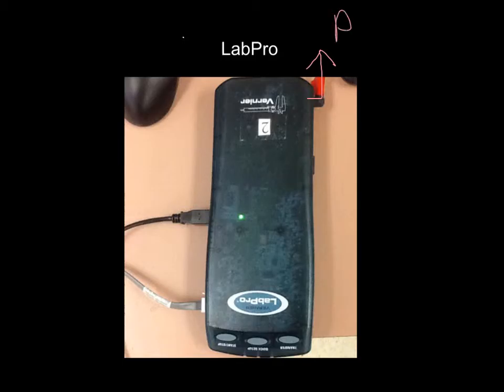This is the power source for the Lab Pro. So if your Lab Pro is hooked up to your computer and it's not showing any sort of lighting, like this little light right here, it probably means that it's just not plugged into the wall. You don't have any power for it. So you do need to make sure that you hook your Lab Pro up to an external power source.